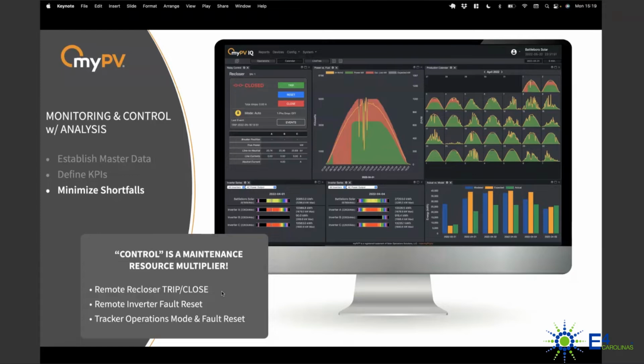The three most common uses of control for O&M are remote recloser trip and close operations, and we're actually going to look at that right here. This is actually a recloser trip and a recloser restore, and we were able to do that remotely. Next, remote inverter fault resets. Not all faults on inverters require a technician to touch it. And if an inverter can be put back into service, you are literally enabling the inverter to continue operating until a technician can get there to perform a deeper analysis, saving that energy yield.